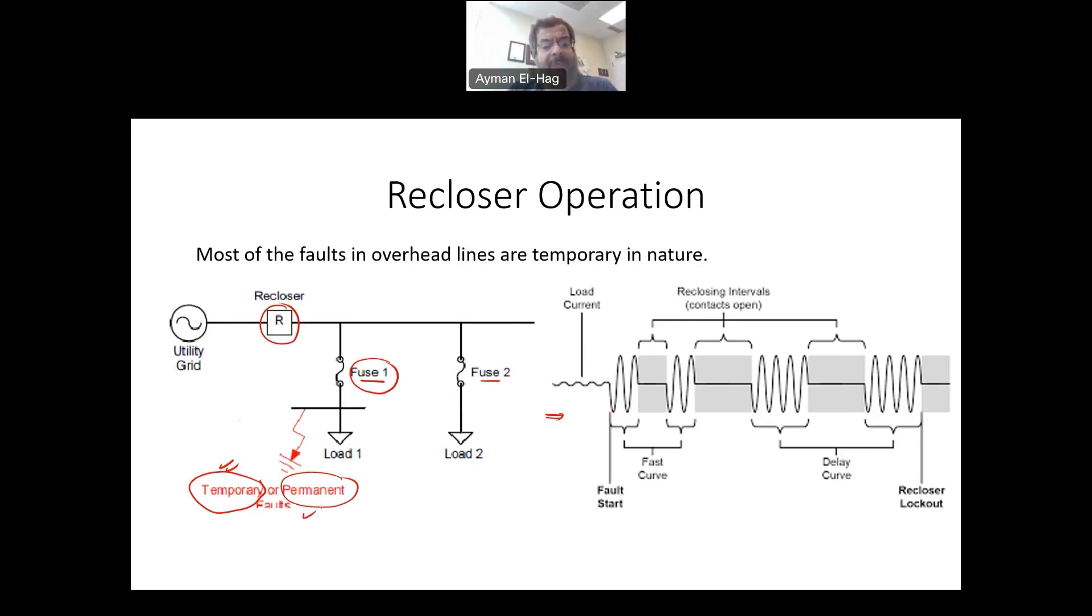Now let's assume that the fault is permanent, a short circuit permanent in the system. Now again, the Recloser will do the same thing. It will try twice, open, close, open, close very fast to protect the fuse.